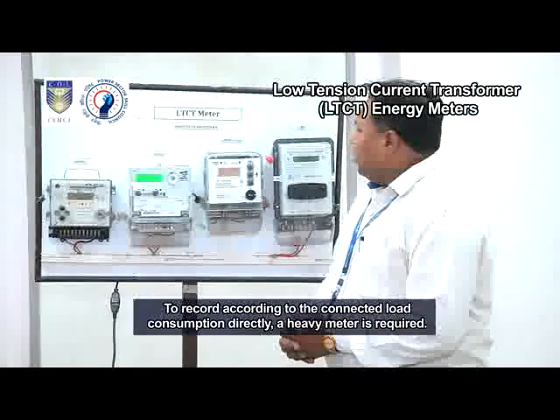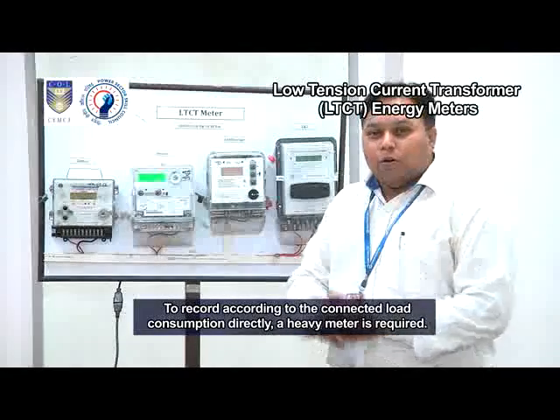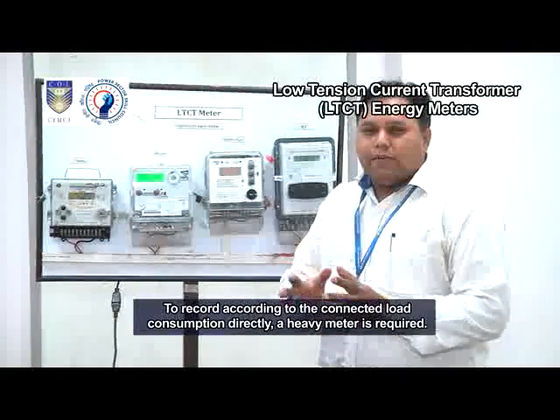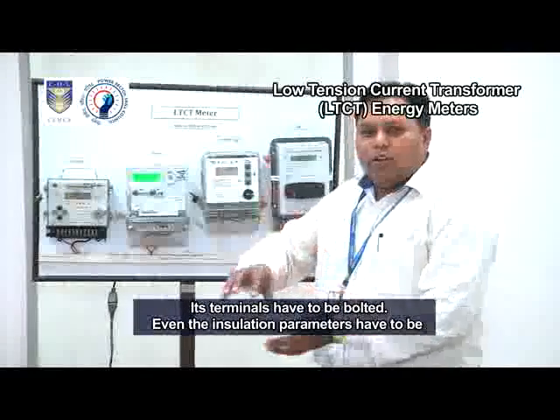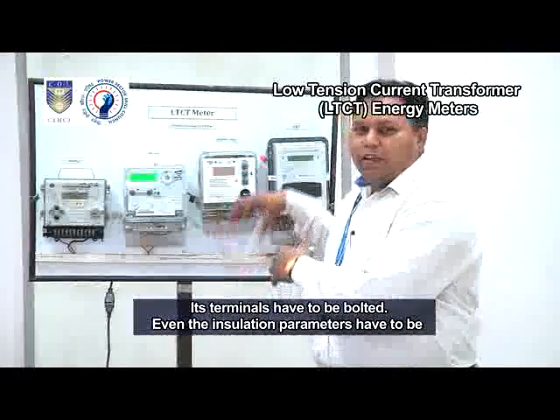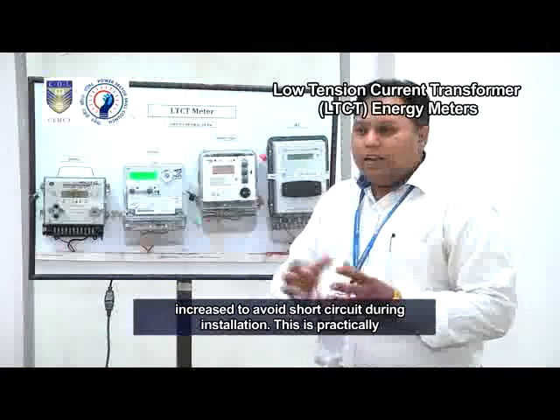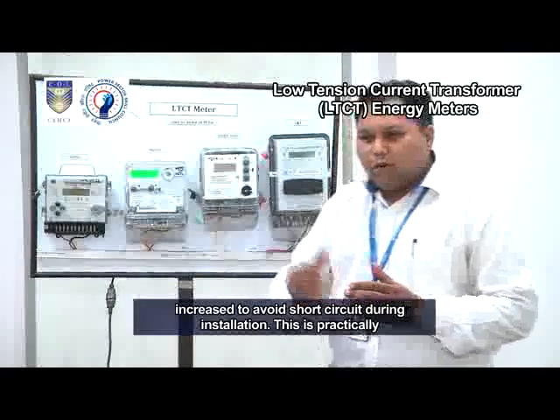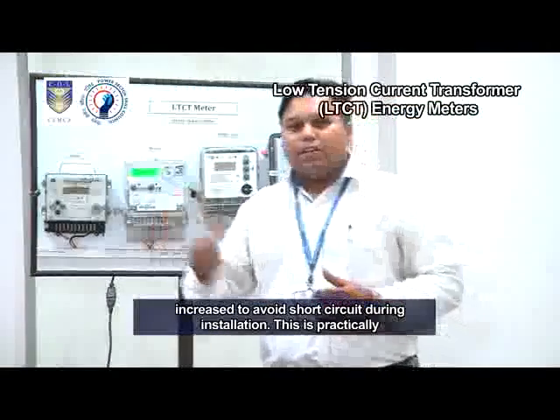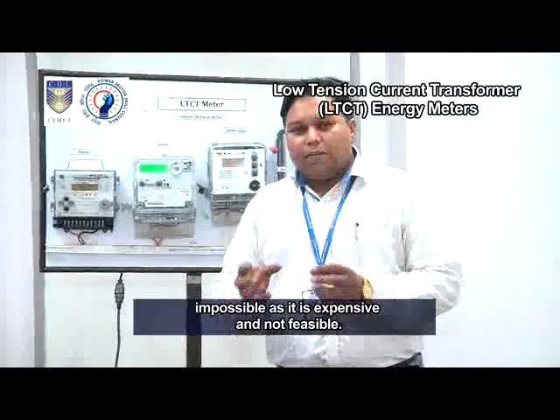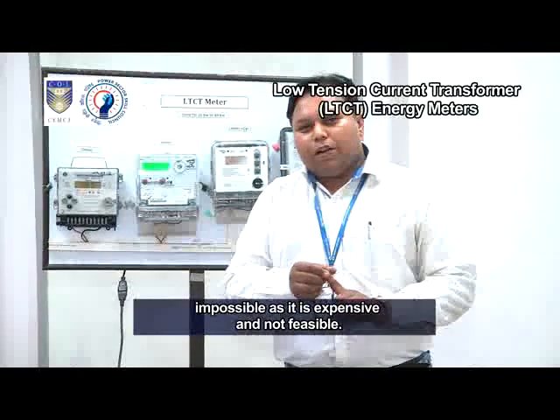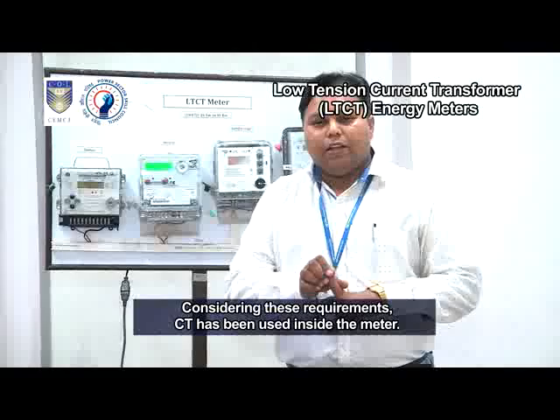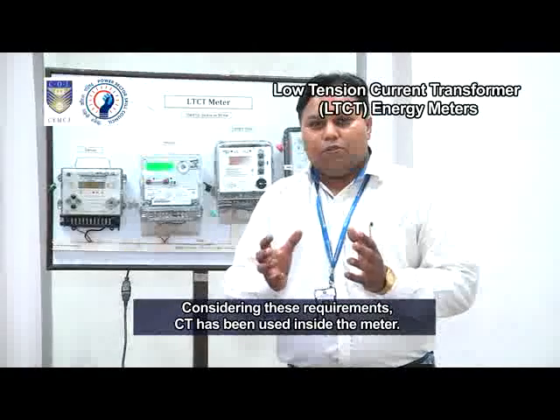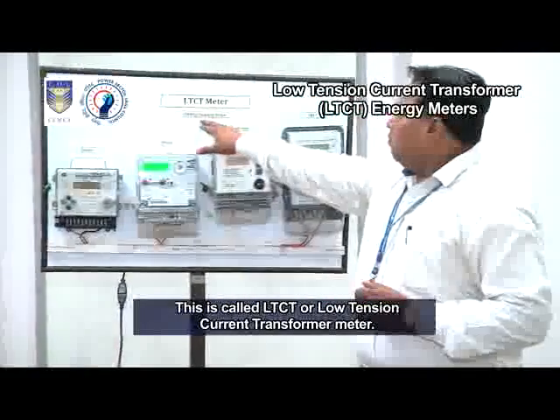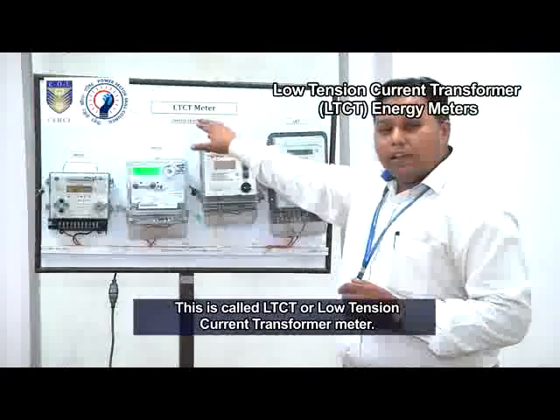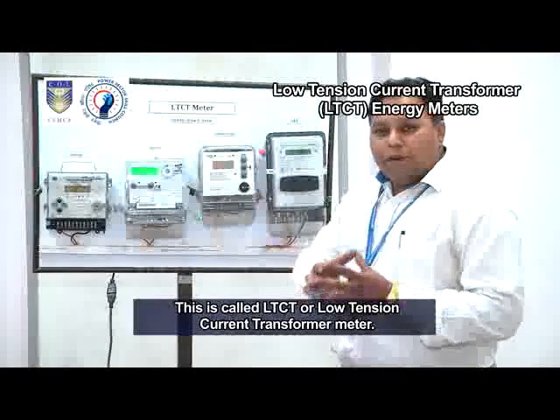To record according to the connected load consumption directly, a heavy meter is required. Its terminals have to be bolted. Even the insulation parameters have to be increased to avoid short circuit during installation. This is practically impossible as it is expensive and not feasible. Considering these requirements, CT has been used inside the meter. This is called LT-CT or Low Tension Current Transformer meter.